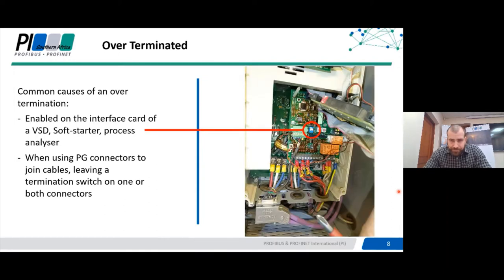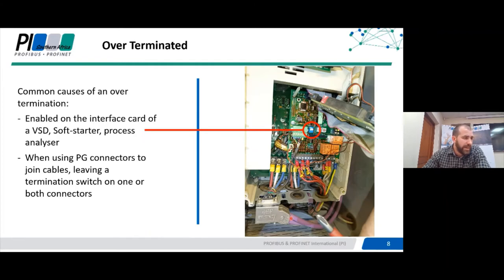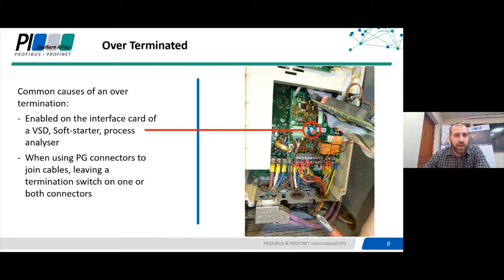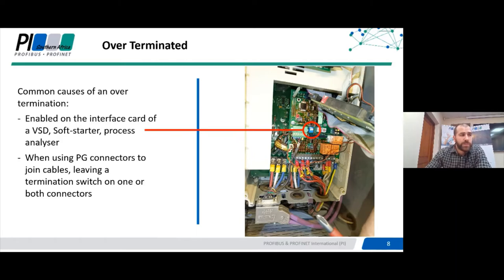In this picture you can see the cover has been removed off a VSD. The Profibus cable comes into a sub-D9 connector and then daisy chains out, so this is not the end of the segment — it's actually the middle. This connects to the chassis of the VSD, and a cable runs up to a Profibus interface card. On this interface card you have indicator lights and two rotary dials to hard-set the Profibus address, which obviously has to be unique. There's also a double-pole blue dip switch visible — it's in the up or on position. By turning this on you are enabling the resistor circuit built into this card.